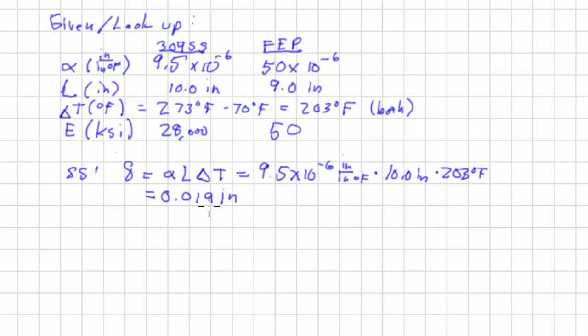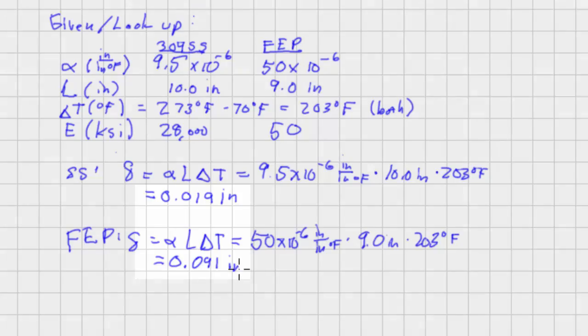For the FEP, our deflection is going to use the same formula, just different numbers. So the FEP has a coefficient of thermal expansion of 50 times 10 to the negative 6th inches per inch degree Fahrenheit times 9.0 inches times 203 degrees Fahrenheit, and that will have it expand 0.091 inches. So you can see this is a much larger deflection than this because of the coefficient of thermal expansion.